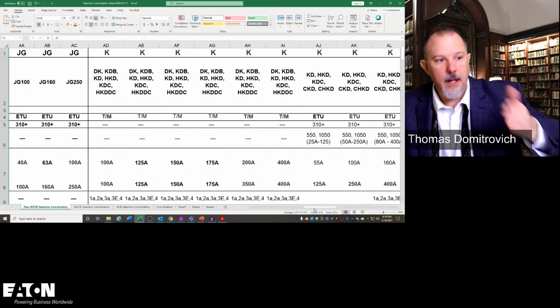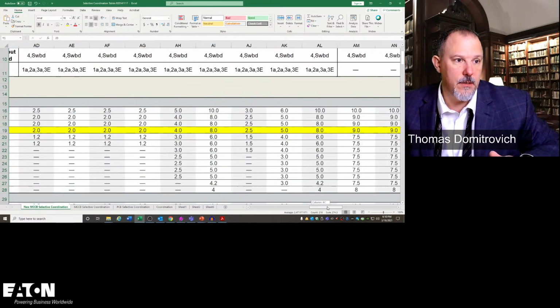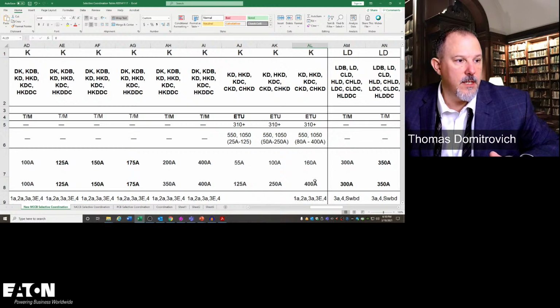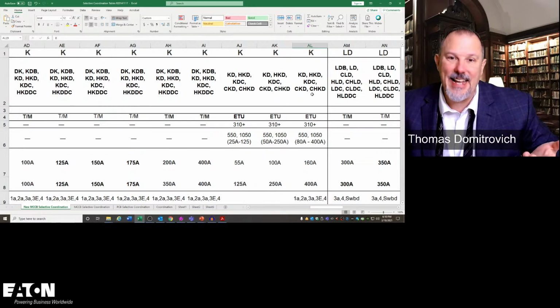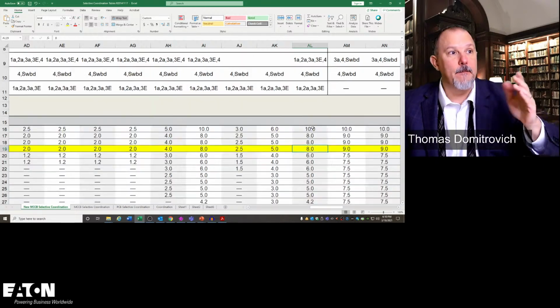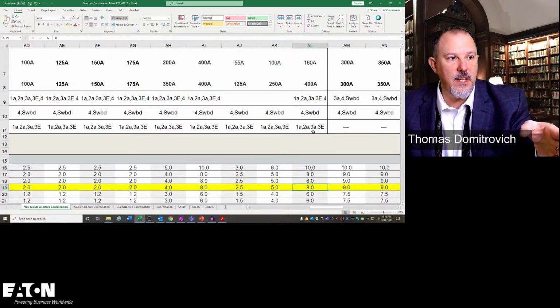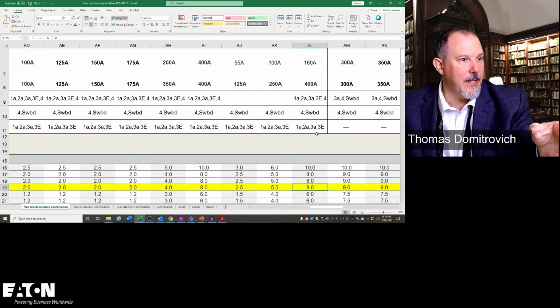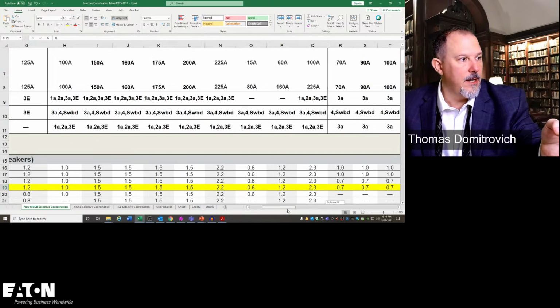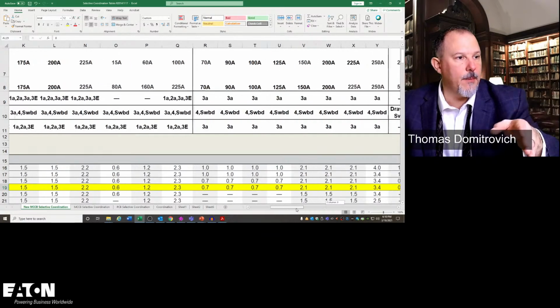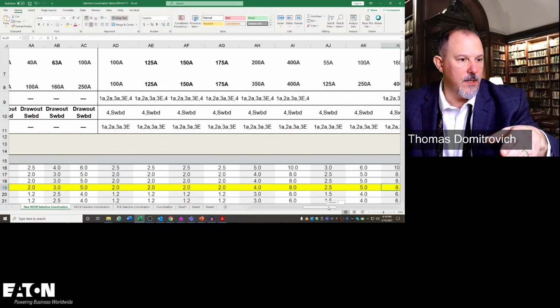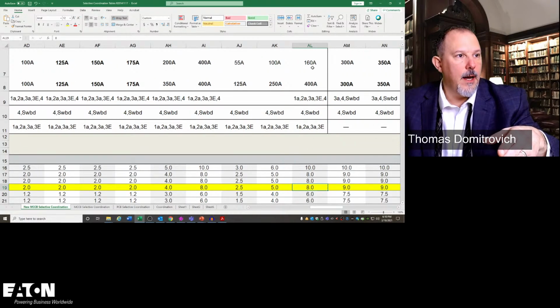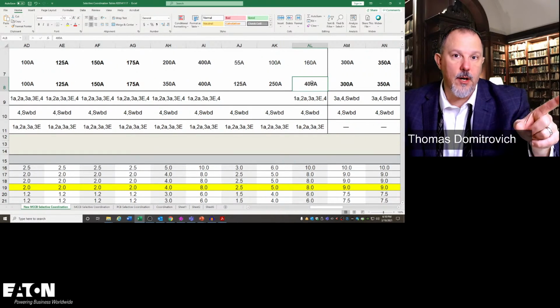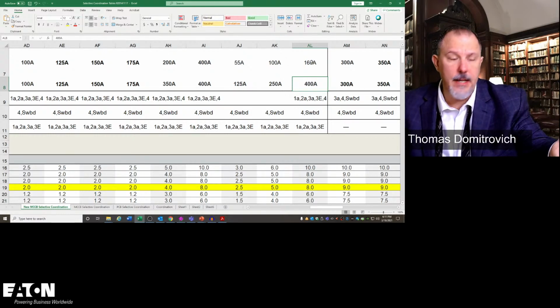Now, we're going to go up. We're looking for 8,000 amps. Here's another 8,000 amps. This is a 400 amp frame, 160 amp trip, KD breaker. Look where I can put this. I can put this in any one of these panel boards. I can put it as a main in my panel board 4. Is that the main? No, the main's the top row. Where's 8,000? Right here. Now remember, this is a 400 amp frame breaker, probably the same breaker as this, but it has an electronic trip unit. I can adjust it down to 250 long time pickup. And look, I can have it as a main in a 1A, 2A, 3A, 3E, 4.